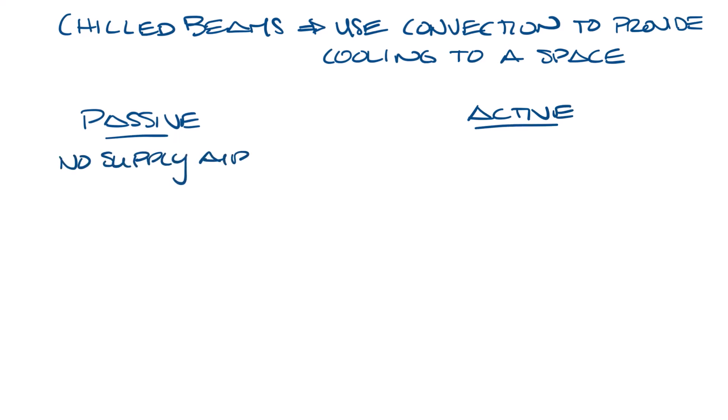Passive chilled beams have no supply air inlet. They use natural convection currents to cool the space and a separate system is used to provide ventilation air for the space. Active chilled beams have a supply air inlet for ventilation air. So let's look at these two types separately, starting with passive.